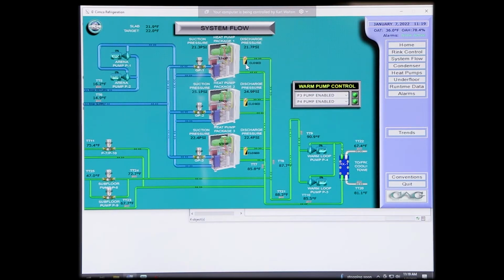You see the Belimo valves here for the warm glycol for the condenser cooling. You'll see those read open when the compressor calls to start. You're also going to see your glycol pump here, your cold glycol pump mounted on the chiller skid. You'll see that start and you'll see a green band fire into here. Okay? And again, based on rotation, it depends on which one is going to start first. It's an auto rotate, so we'd have to look to see which is the next call to start. In the bottom here, we have some more temperature sensors, P7 and P10, which I will show you later. Your subfloor pumps, P9 and P8. Again, more sensors.